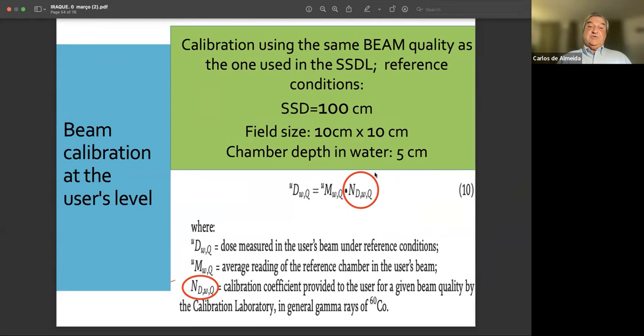But it's true that very few institutions nowadays still have cobalt 60, where the calibrations are done. If you use cobalt 60, it's very simple, because you have the readings of the instrument corrected for the influence quantities. And when you use the calibration coefficient, you get straight the dose to water.